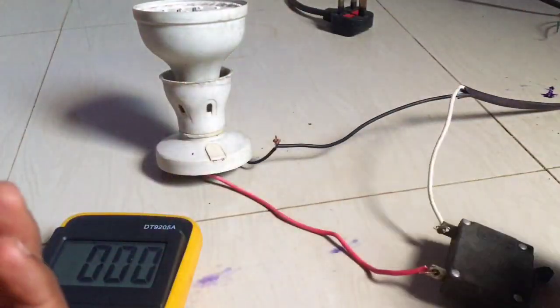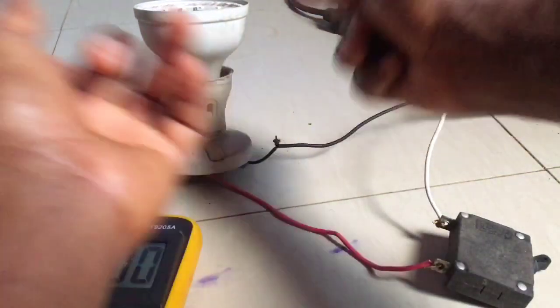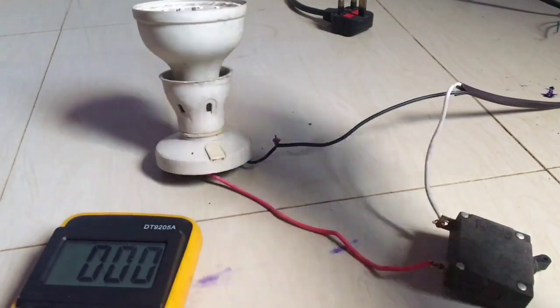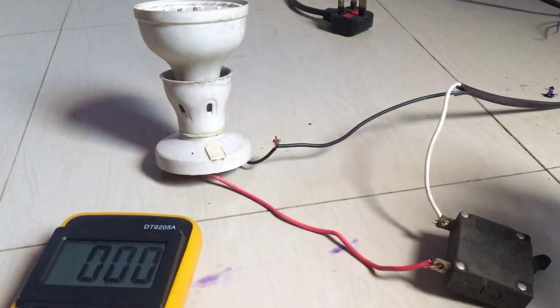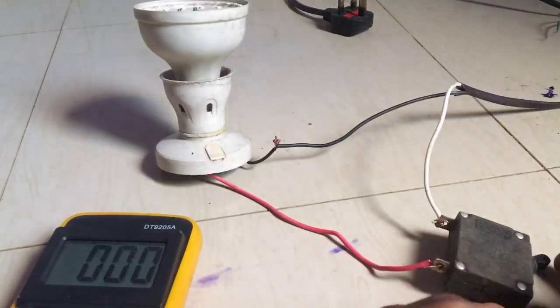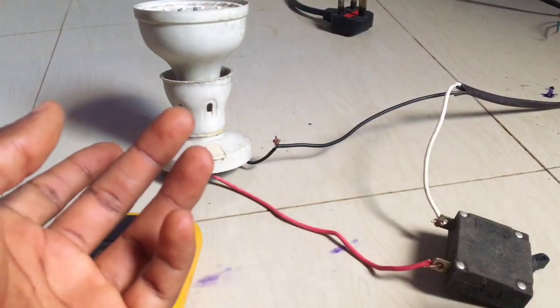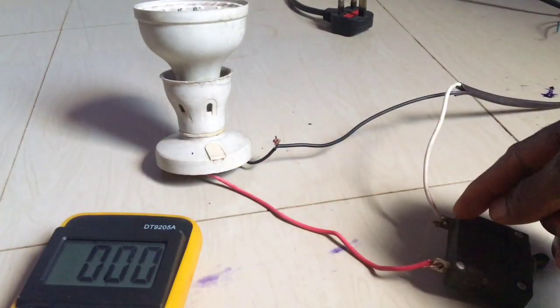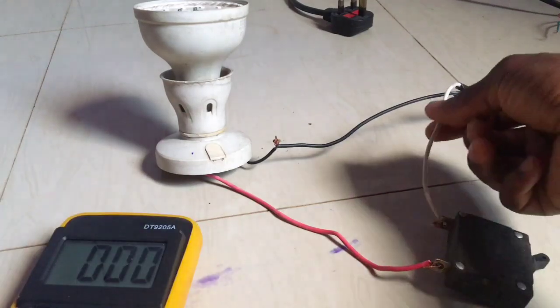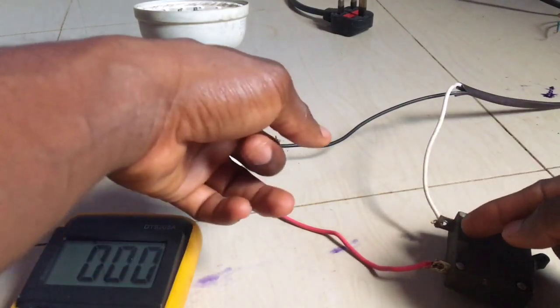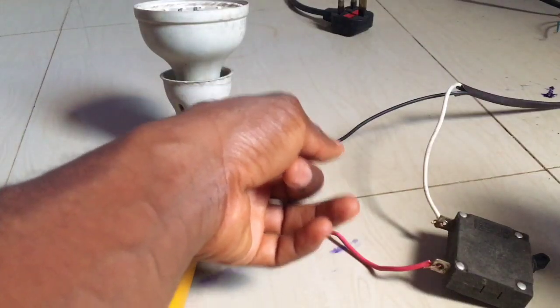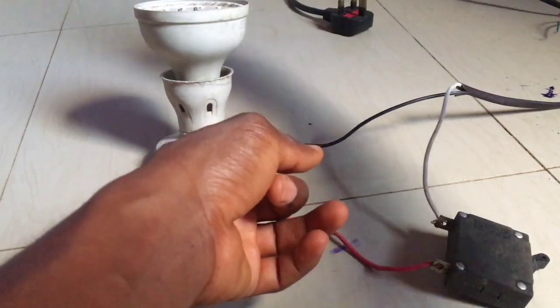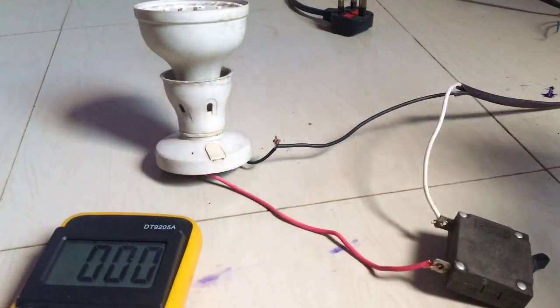You test for voltage across the lamp holder terminals while your switch is on. If you have voltage there, then know that it's either your bulb is bad or your lamp holder is bad. If you don't get voltage here when the switch is on, two things are involved: either this line is not true or your switch is bad. To know if this line is true, we test this terminal and any other neutral. To know if the neutral link is bad, we test the voltage across the neutral link and any other functional live wire. All right, so this is just how it's done.